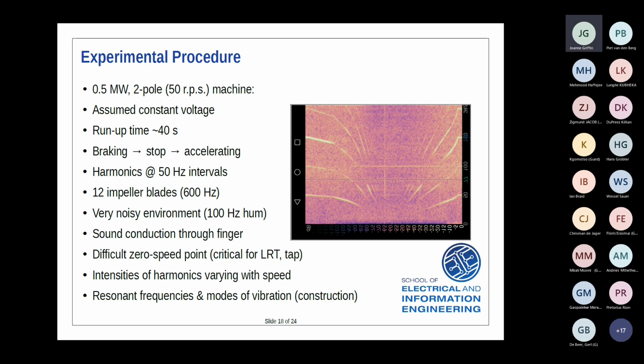I'll take this trace here. The machine is running full speed backwards. We disconnect the machine momentarily, so you can see it's starting to coast down, slowing down due to friction and windage losses.